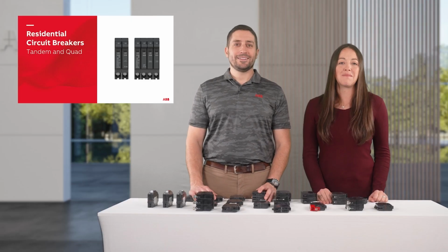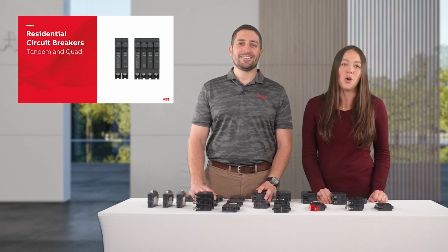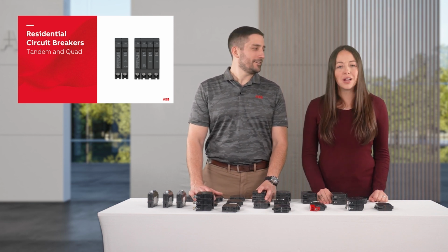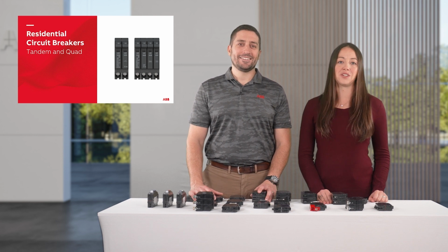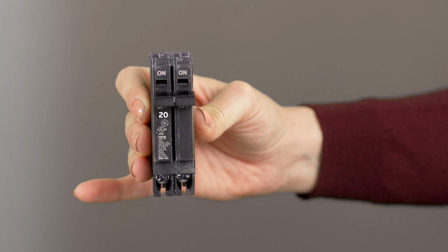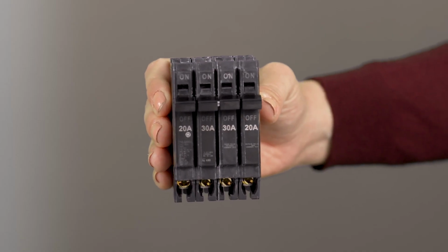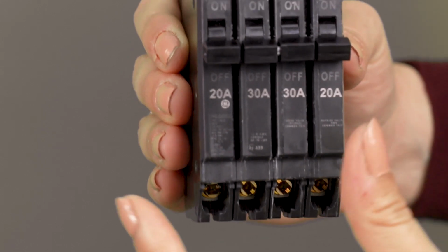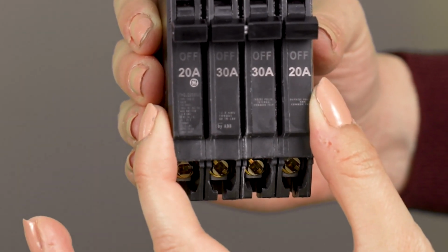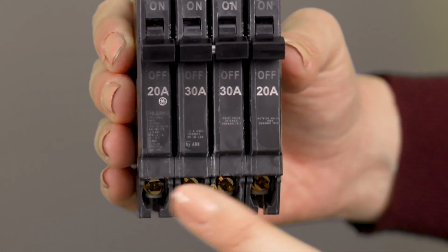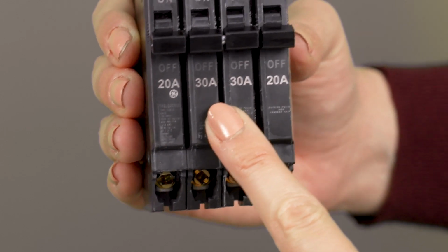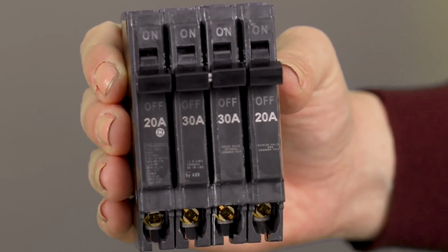What if you could have twice the number of breaker spaces in the same load center? We offer tandem and quad breakers, which are great for when you need to save space in new construction or renovations. The tandem breaker has 2 independent 1/2 inch single poles that occupy 1 breaker space within the load center, ranging from 15 to 20 amps per pole. The quad breaker requires 2 breaker spaces, but they have 2 independent 1/2 inch outer single poles that range in amperage from 15 to 20 and 1 independent interior 2-pole breaker ranging from 15 to 40 amps.